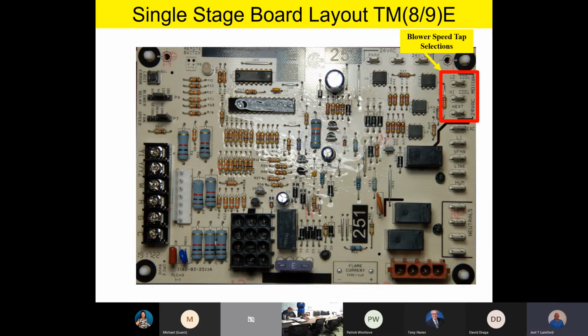Now at this time, I'd also like everybody to really take a close look where it says low cool and high cool. So even though this TME, this basic single stage heating control board, is just a single stage heating unit, we have the capability of having a low cool and high cool for a 2-stage piece of equipment. As a matter of fact, one of the things I really, really like about our Johnson Controls and Champion TME board here, furnace, is the fact that even though it's single stage heating, this thing will literally hook up with anything in our inventory except our 20 and 21 SEER Momentum unit. So if you have a 17 SEER 2-stage unit, this thing is perfectly compatible with that.